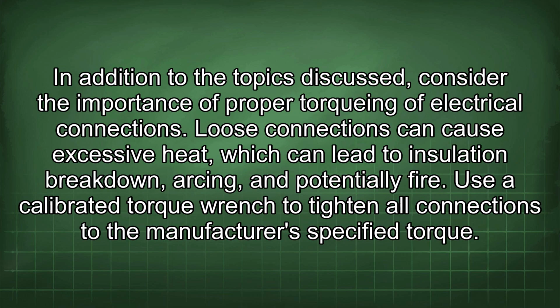In addition to the topics discussed, consider the importance of proper torquing of electrical connections. Loose connections can cause excessive heat, which can lead to insulation breakdown, arcing, and potentially fire. Use a calibrated torque wrench to tighten all connections to the manufacturer's specified torque.